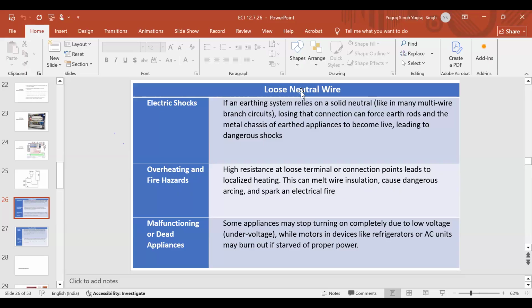Then overheating and fire hazards, high resistance at loose terminal or connection points lead to localized heating. You see that sparking and other things. This will burn your gadget also. This can melt wire insulation, cause dangerous arcing, and spark an electric fire. Now, there are appliances which may not properly work. They may become dead. Some appliances may stop turning on completely due to low voltage, while motors in devices like refrigerator or AC unit may burn out. This is neutral wire being intact is very, very important. Generally, you will find all the burning is there in neutral conductor only.